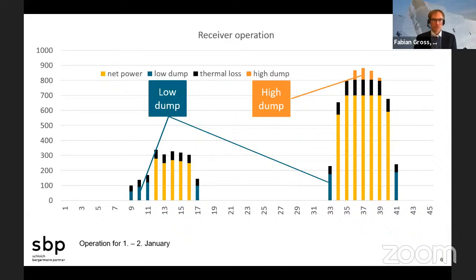The initial receiver designs would only start operating above a lower threshold of 30% of nominal load, and not beyond 100% of nominal load. Already in the first days of January, you would see what kind of problem that causes. It's quite easy to supply heat that is already interesting but would be rejected by the receiver because the cut-in is so high, and on the other hand, even in winter, it's possible to supply more heat than the receiver could take.